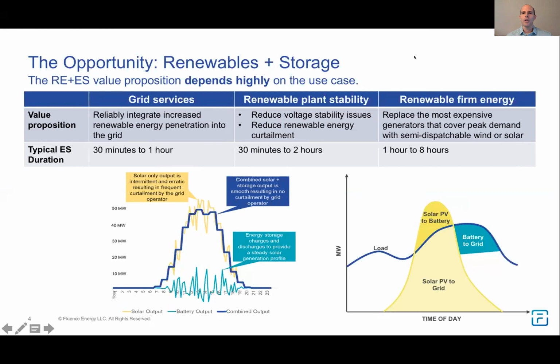Here, you're essentially taking some of the PV energy produced during the middle of the day and making the facility dispatchable by time-shifting that energy into other parts of the day, typically late afternoon or evening as the load comes up. You could shift to other times too, if there's a reason to. To do this use case, you would need more battery—typically in the 1 hour to 8 hour range of battery duration for a renewable firm energy use case.